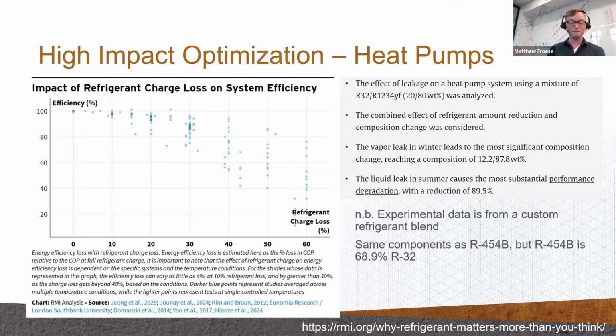and the output from that machine changes. So most of the time, what we get at the control layer is, did we ask it to turn on? Is it running? And are we getting any alarms? You might not see that you've lost 40% of your refrigerant and maybe 50% of your efficiency. And if you're in Manitoba, where 50% of your efficiency might mean the difference between making sense to run a heat pump versus just running a baseboard heater, that's a big deal. And missing that, I think, is a big deal.